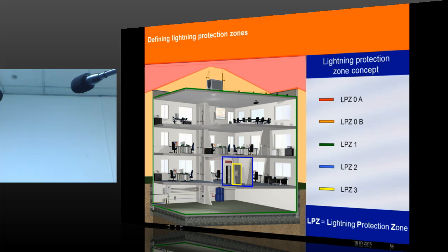So now, how to achieve lightning protection zone 1? To call an area inside, you imagine that this is the outer wall of the building, and I want to call this place where I am standing LPZ 1. What are the conditions? Condition number 1 is that magnetic influence in this area shall be reduced. You cannot have a big amount of magnetic radiation. It has to be controlled. It has to be reduced. Conducted surges through lines means potential difference. Transient currents, transient voltages through lines need to be reduced. Equipotentialization needs to be achieved throughout the wall, throughout the first place.